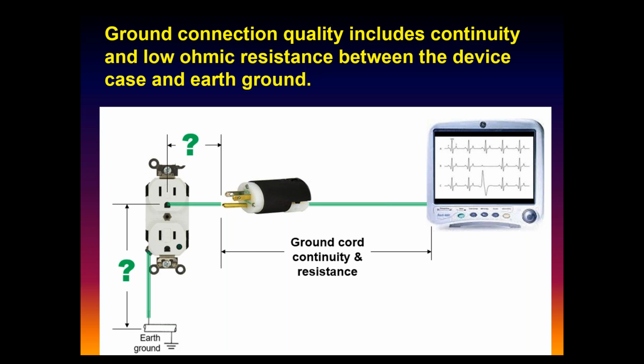When you think about the effectiveness of the ground, in order for the ground to be effective at all, it also has to have good ohmic conductivity to the physical dirt. You could have your 0.5 ohms or so from the pin to the machine, but there's also going to be resistance between the pin and your sloppy outlets. You can always see this if your plugs get warm. You've got a high resistance and normal current between hot and neutral, so you're getting power loss. Power, remember, is I squared R.